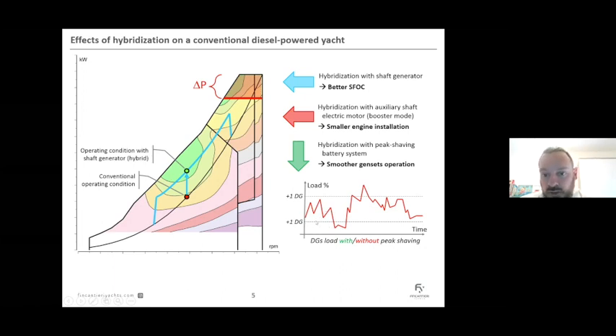Below the bottom dashed line, one diesel generator will be taken offline, only to be brought back online a few minutes later. Due to a sudden spike, another generator may be brought online for just a few minutes and then switched off again. By installing an energy storage system acting as a peak shaving system, I can achieve smoother operation of the gensets. They will work at an even load, while batteries compensate for spikes by discharging and recharging. If the genset layout and battery power are studied properly, I can avoid continuously bringing more gensets online and offline. This means the gensets will work better and be more efficient.